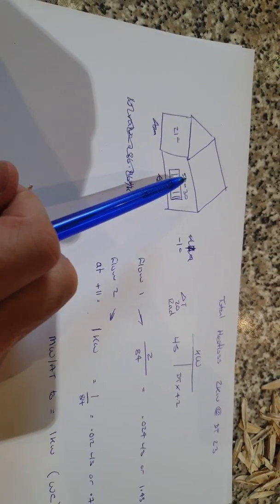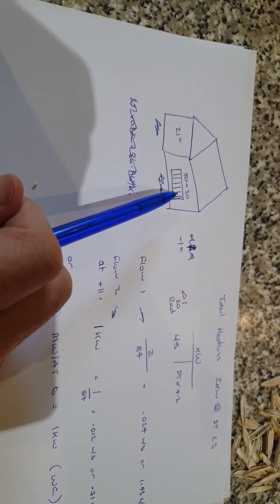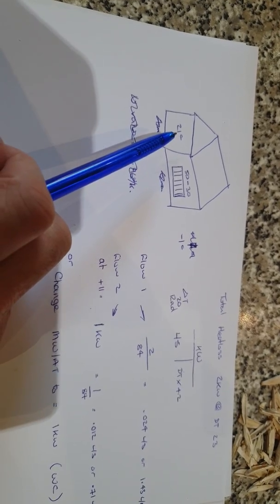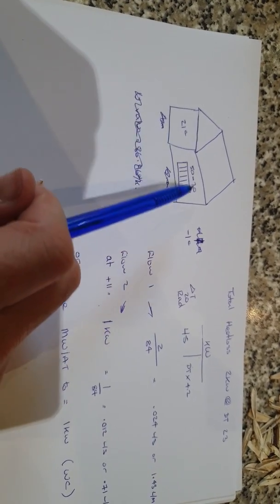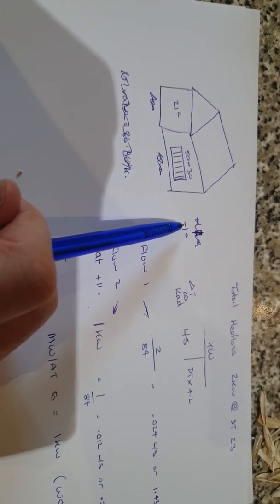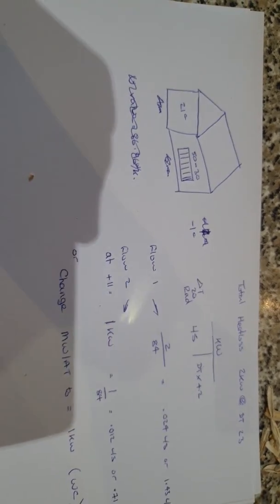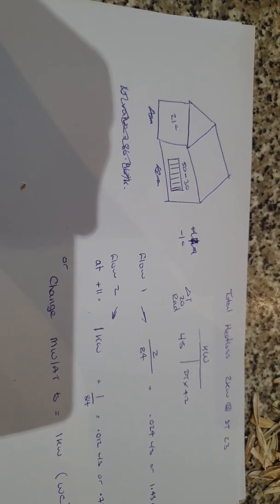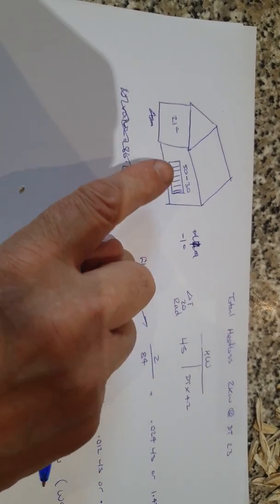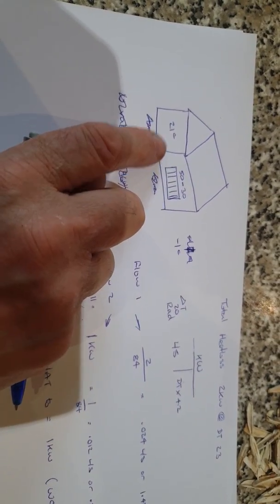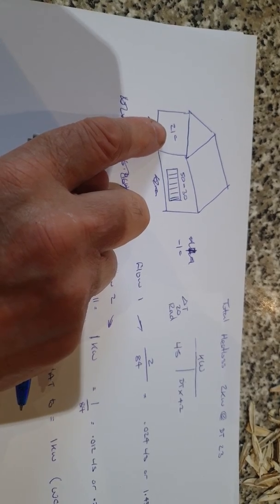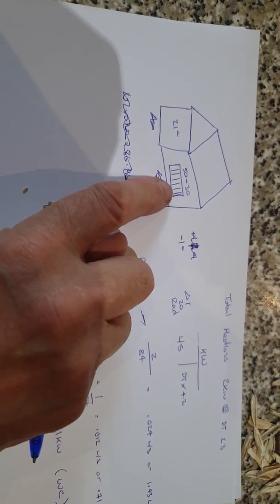When we're designing a heating system, we're taking a set of criteria to design to, such as an internal temperature of 21°C and an external temperature to function at minus 1°C for London, for example. Basically, we're calculating the heat loss for the property or for the room at 21°C internal and minus 1°C outside.